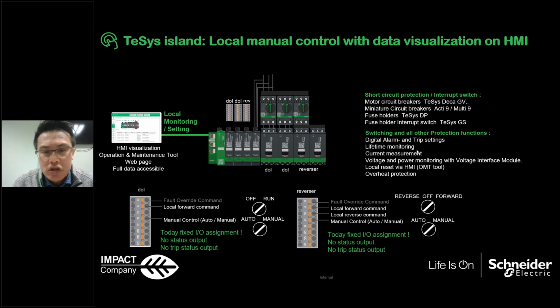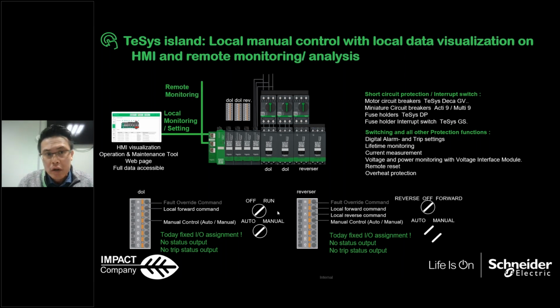If you don't want to communicate the contactor to the system locally, you can achieve remote monitoring and remote analysis. As I mentioned, this basically communicates with an open protocol. So you can communicate to the PLC, or even to the power SCADA, and then reach the bus coupler for remote monitoring. All the data can be remotely monitored in your dashboards, or you can remotely control the on-off of the contactors and their status. So you can achieve local monitoring, local setting, manual control, or even remote operation.